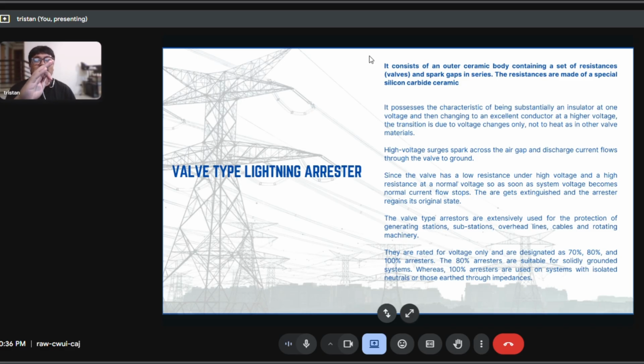In high voltage surges, the spark across the air gap and discharge current flows through the valve to the ground. So since the valve has a low resistance under high voltage and a high resistance at a normal voltage, as soon as system voltage becomes normal, current flow stops. The arc gets extinguished and the arrestor regains its original state. So the valve type arrestors are extensively used for protection of generating stations, substations, overhead lines, cables, and rotating machinery.